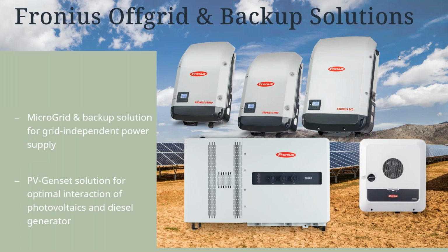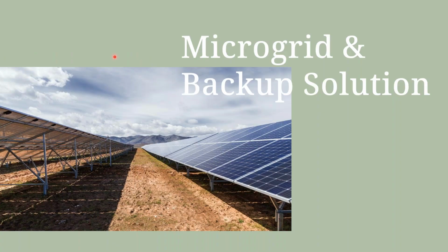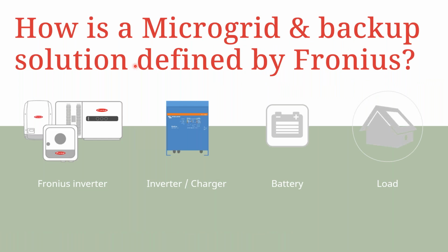So let's get started and look at the Fronius Offgrid and Backup solutions. A microgrid and backup solution is really a solution that is engineered to give you grid independent power supply. In addition to that, when you bring a PV genset into the mix, we are looking at a solution that would allow optimal interaction between the PV system or the solar system and the diesel generator, or all generators, if there are a number of generators in that setup. When it comes to the backup and microgrid solution, we have a way of looking at it from Fronius in terms of how we define it. In this case, we are talking about a setup that includes the Fronius string inverters, in combination with an inverter charger, then a battery storage, and then the load that is supported by this setup.